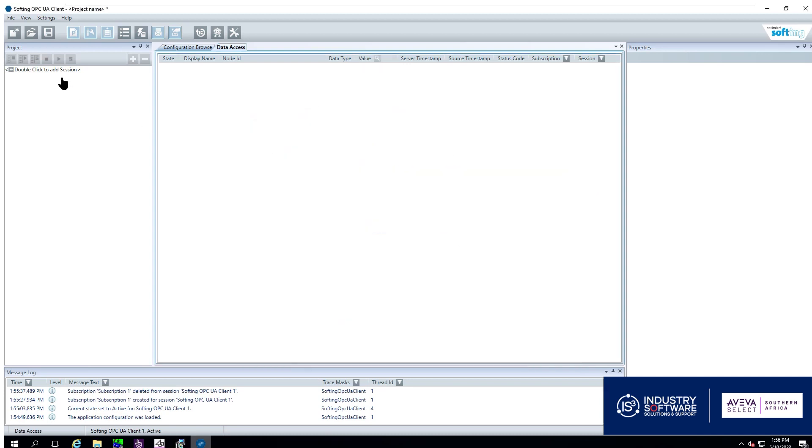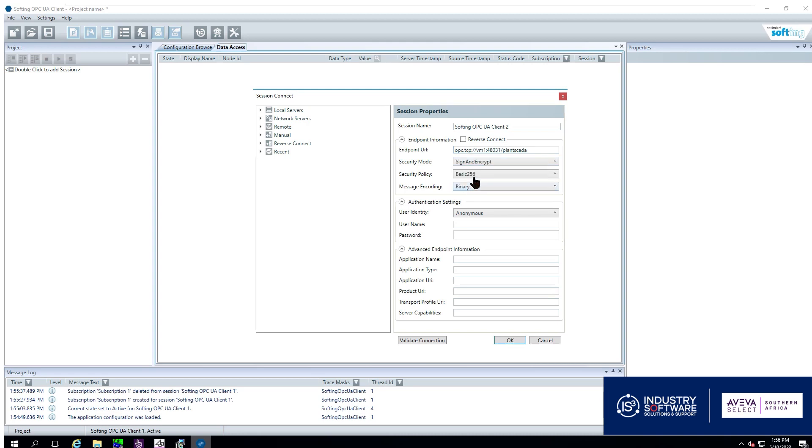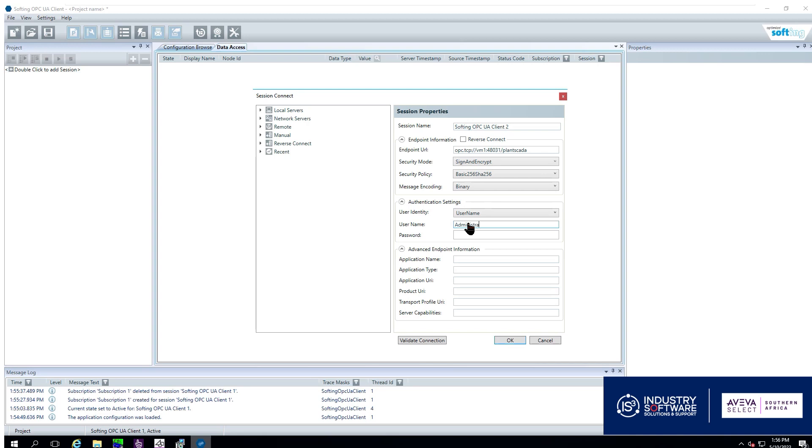We go and we add another session and we input our endpoint URL. When we configured it it would have told us that our security mode is signed and encrypted and it gives us the correct security policy to use. We are now going to use the username which in this case is the standard Windows admin login for this configurator. And so I put in the password and we validate our connection.